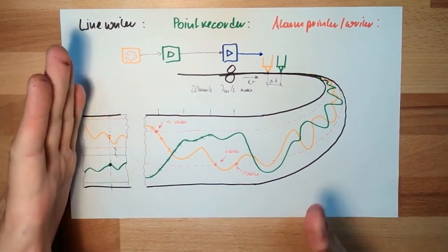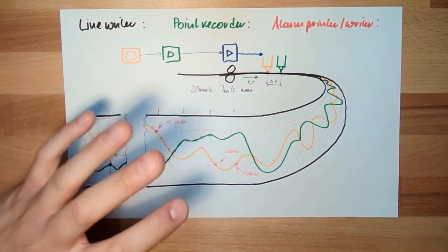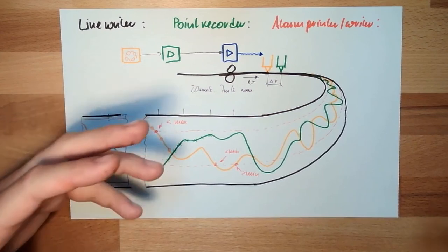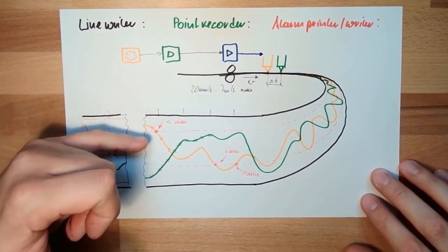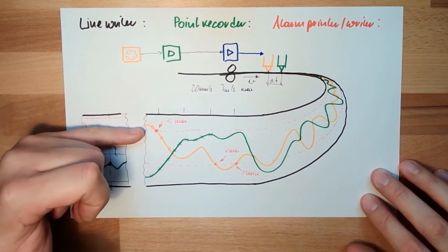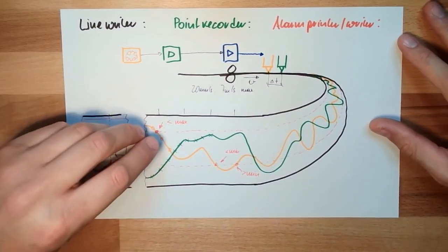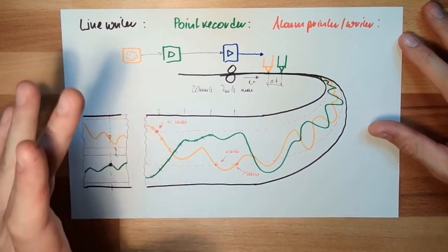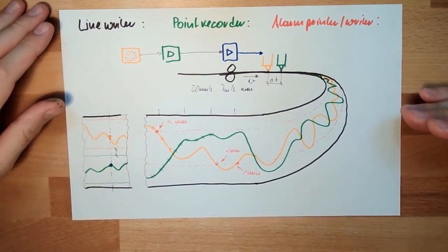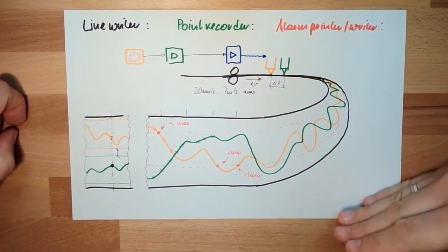If there's a separate database, and some value is leaving the Sollbereich, the wanted area, it's going to an alarm area, or usually there are two areas. One is the warning area and one is the alert area. One is yellow and one is red. Usually warning means there might be something, and alert means there is for sure something, look at this. These things are stored in a database, chronologically saved, and you can watch it, exactly like an alarm printer.